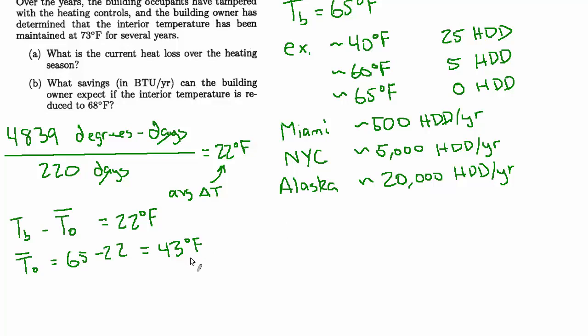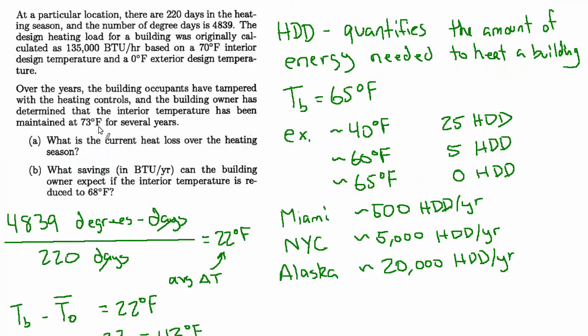And now we're ready to take into consideration the specific attributes of this building, which was designed for a worst case scenario heat loss of 135,000 BTUs per hour when the delta T is 70. Indoor design temperature of 70 degrees and an exterior design temperature of 0 degrees. So let's figure out how much heat loss per degree based on those design conditions. We'll do Q dot design divided by the design delta T. So that's 135,000 BTUs per hour divided by 70 degrees Fahrenheit. And we get 1,929 BTU per hour per degree Fahrenheit. So for every additional degree Fahrenheit in the delta T, it's going to take an extra 1900 BTUs per hour to make up for that heat loss.